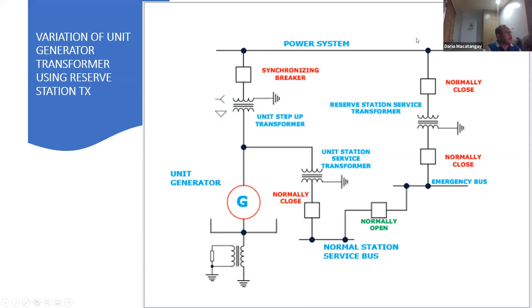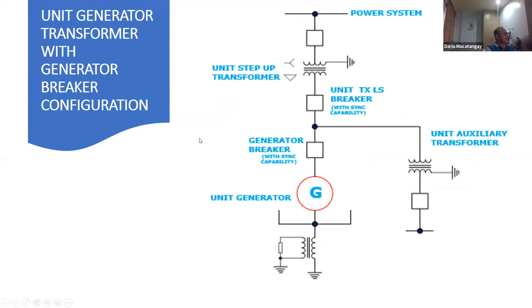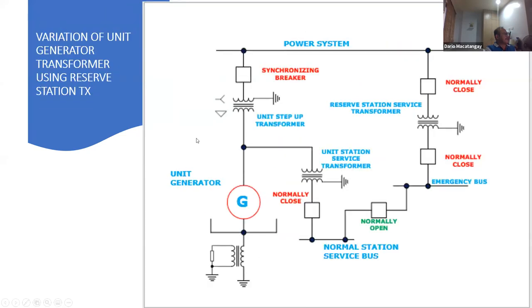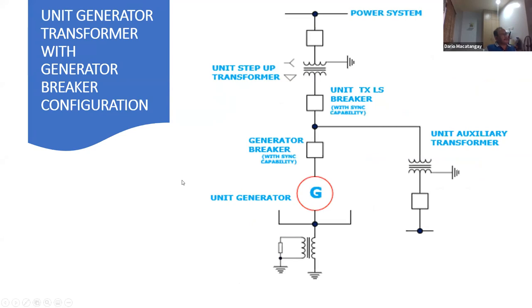Okay. Now, the other type is this unit transformer with generator breaker configuration. Okay, this is typical in most of the plants that I've seen here. We have a generator breaker, and then we have a unit transformer low side breaker, and a unit transformer high side breaker here. Okay, now you have a unit auxiliary transformer that supports the loads needed for the operation of the generator and the turbine.